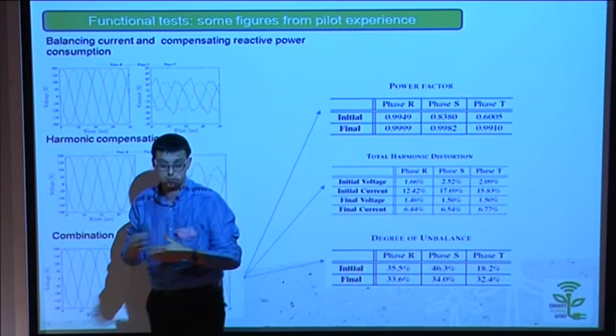In terms of harmonic distortion, the first situation before the connection of the IDPR is that we have, in terms of voltage, up to 2.5% distortion, and in terms of current, about 17%. After the connection of the IDPR, we reduce the current distortion to 6.5%, and we also correct a little bit the voltage. This means an increase in the quality of service that we are supplying to the rural consumers.